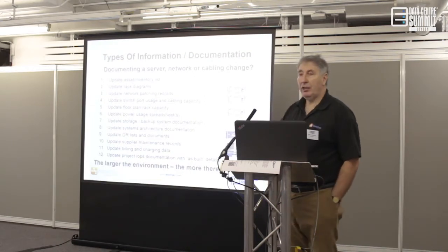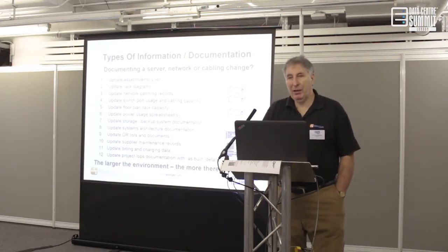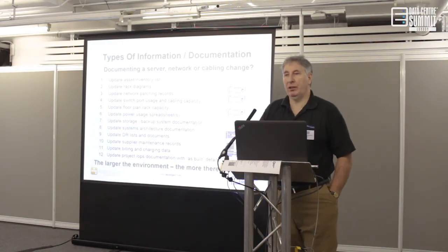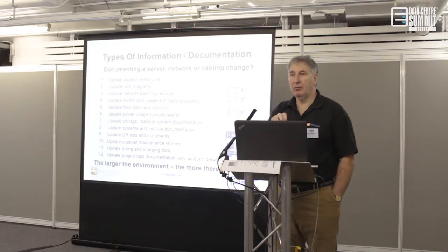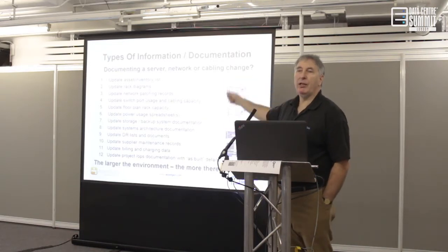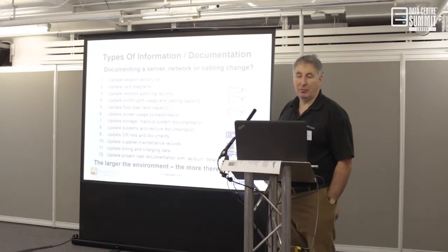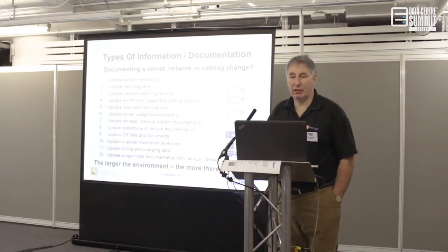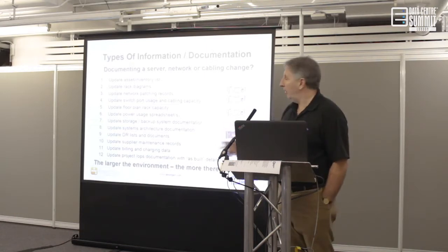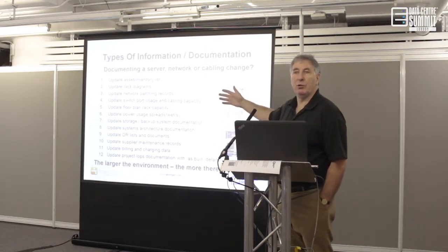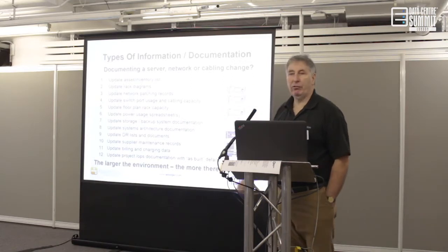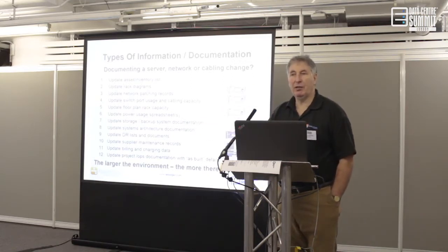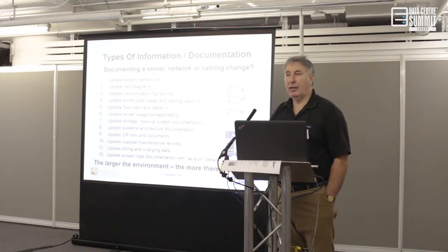And when we go and actually update, patching is only one of the things you update when you actually change things. So if I was to put a server into a rack and connect it up to a switch in another rack, probably I may have to update all of these different things. So I may have to update asset lists and inventory lists, rack diagrams, which could be in Excel or Visio or CAD, patching records, which we were talking about. How many switch ports do we have free? I've just lost one of them. So actually I'm decrementing the capacity of both the power and the network.